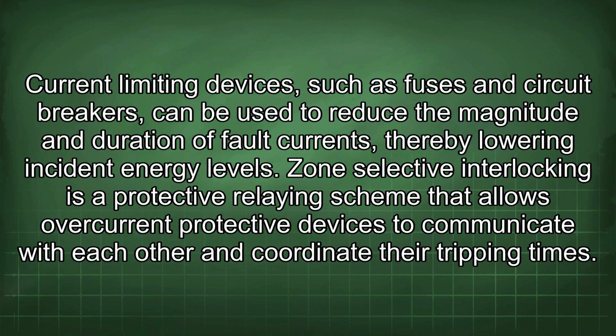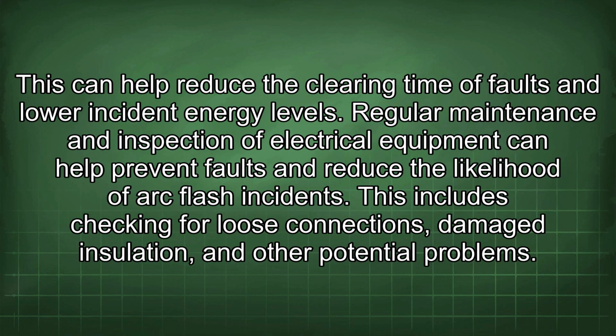Zone-selective interlocking is a protective relaying scheme that allows overcurrent protective devices to communicate with each other and coordinate their tripping times. This can help reduce the clearing time of faults and lower incident energy levels. Regular maintenance and inspection of electrical equipment can help prevent faults and reduce the likelihood of arc flash incidents. This includes checking for loose connections, damaged insulation, and other potential problems.